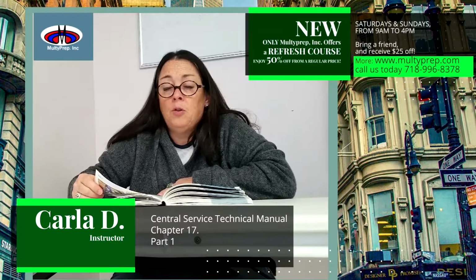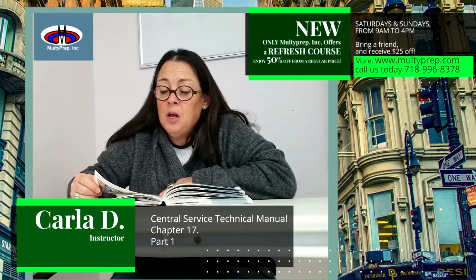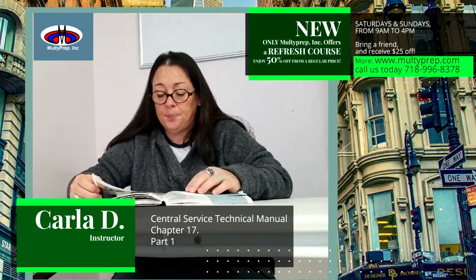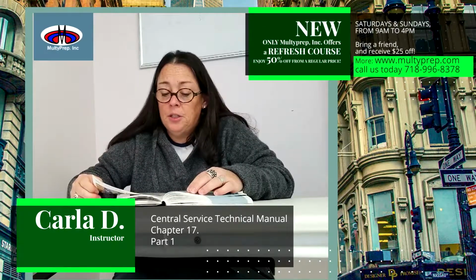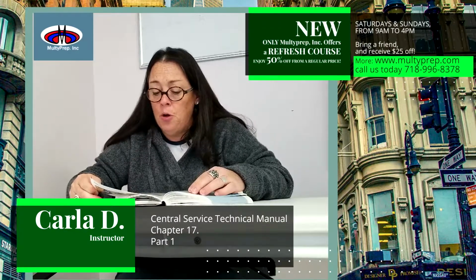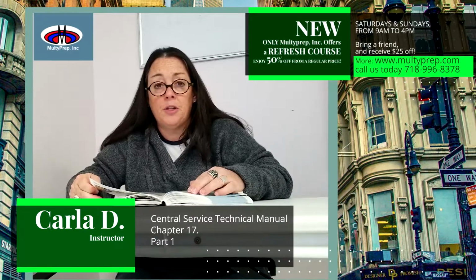Internal chemical indicators. Internal CIs are placed inside the package and provide evidence that the sterilant penetrated the package. Note, internal CIs do not prove sterility. See Figure 17.6, which provides examples of some CIs. CIs should be placed in an area of the package, tray, or container considered to be the least accessible to sterilant penetration. Note, the location is not necessarily at the center of the package, tray, or container.